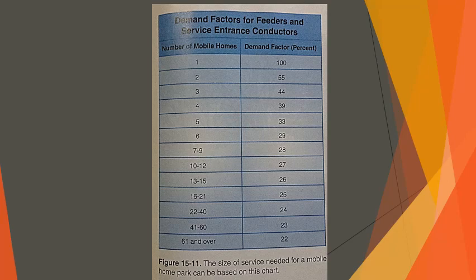Again, to repeat, for example, assume that the largest mobile home that will fit in the park has a calculated load following section 550.18 that is less than 16,000 VA. Section 550.31 requires you to use at least 16,000 VA for each mobile home lot. 16,000 VA times 25 equals 400,000 VA. According to table 550.31, the demand factor for mobile home parks with 22 to 40 lots is 24%. So 400,000 VA times 0.24 is 96,000 VA.